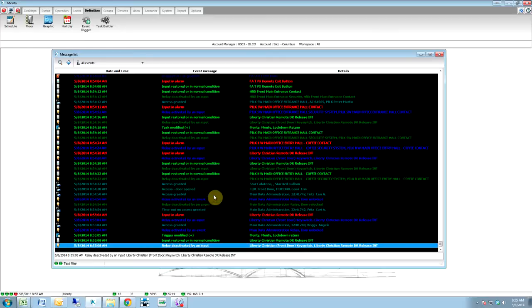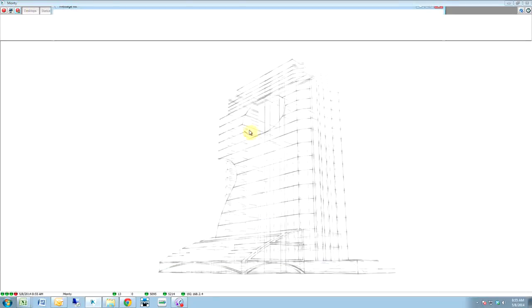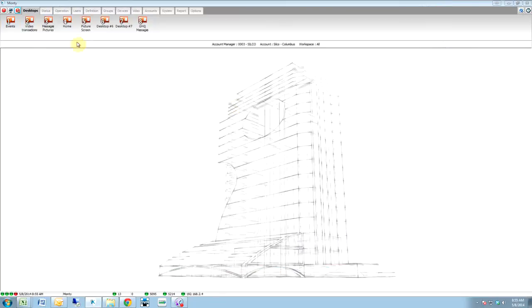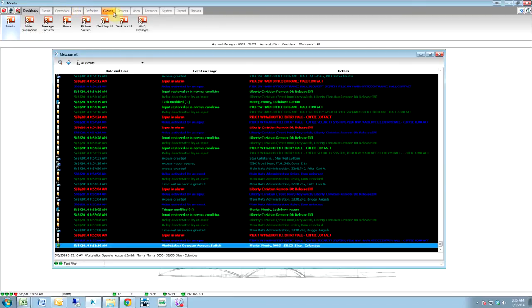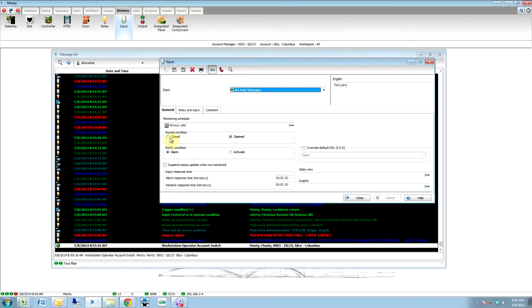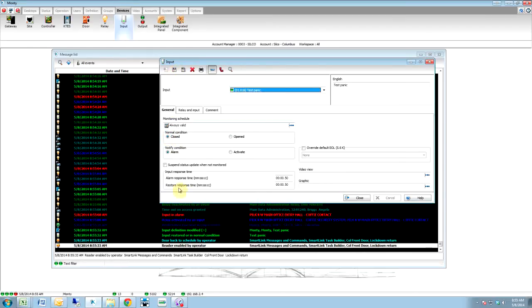So now if we watch the events here — we're just going to watch the events from this information. If we go to input, devices, input, and we select our input — now I'm going to fool it by doing this, but it should run two things. It says door back to schedule by operator, reader — because the input was in alarm. It says input restored in normal condition. Now it says door back to schedule by operator, reader enabled. So now my reader is good.